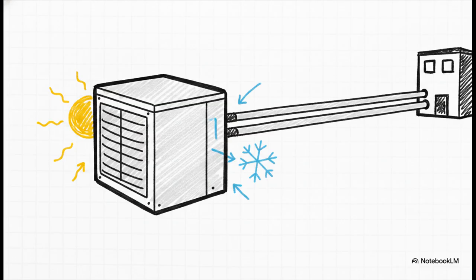It's connected to the building's interior using just 2 refrigerant pipes, exactly like a typical split-system heat pump. The amount of refrigerant in the entire setup is strictly limited to the distance between this outdoor unit and your mechanical area inside. And sure, there are rules for allowable distances, but they can reach hundreds of feet, which is honestly perfectly fine for most commercial and residential applications.